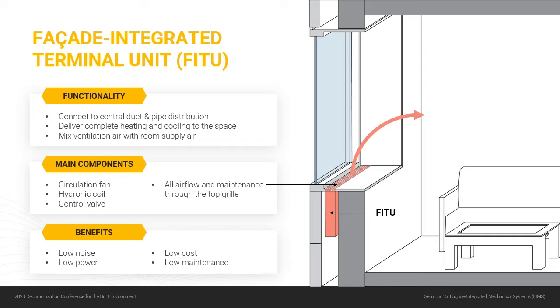Now, the FITU is a pretty simple unit, only a few main components. So it has a circulation fan, a hydronic coil, and a control valve. And that's essentially it. Now, the trick with it is that it has to be able to fit within a narrow cavity. And once you install it, it's essentially sitting behind the existing wall. And the only way you can access that unit is through that top grill in the windowsill. So all the components need to be designed so that you can access it through the top grill, and the airflow, the supply and the return, has to all be through that top grill.